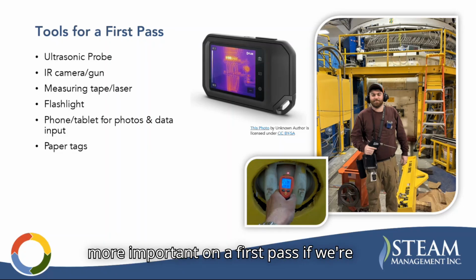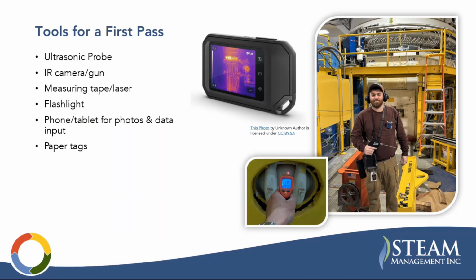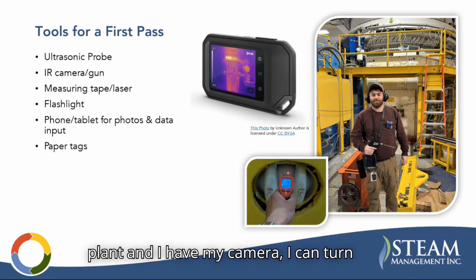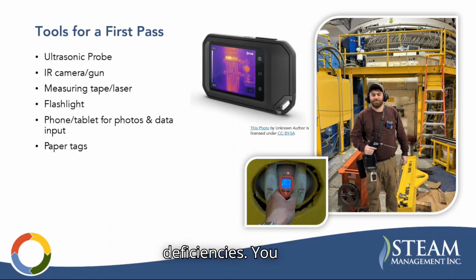Maybe even more important on a first pass, if we're not doing a trap test, is an IR camera or a gun. It can be a really good cheat that I can use. Like if I walk into a boiler plant and I have my camera, I can turn my camera on and scan the room and just see what's on and what's not on. You can immediately see insulation deficiencies.